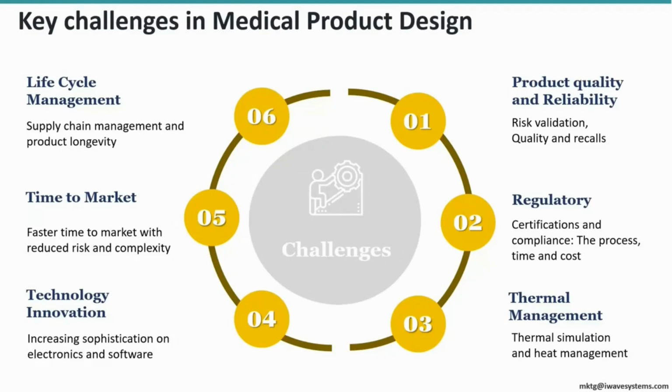Medical devices are always subject to strict safety standards and usability guidelines. One essential consideration is thermal management, in which the IEC 60601 standard regulates the surface temperature for medical devices. Therefore, thermal simulations are an integral part of the design process.